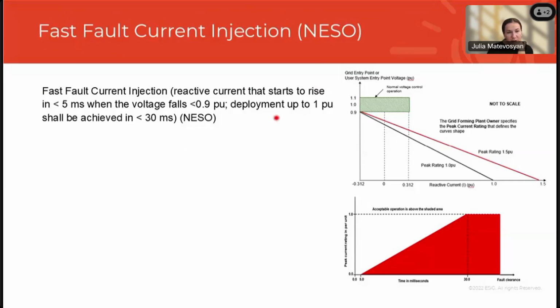National Energy System Operator also defines fast fault current injection. So they expect reactive current to start rising within 5 milliseconds as voltage falls below 0.9 per unit. And deployment of full response shall be achieved within 30 milliseconds.